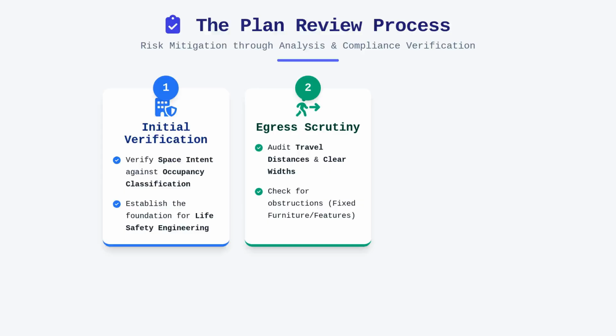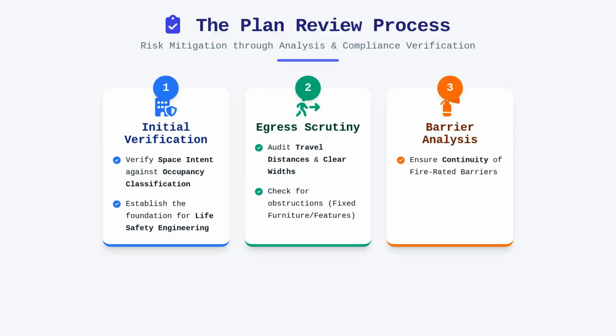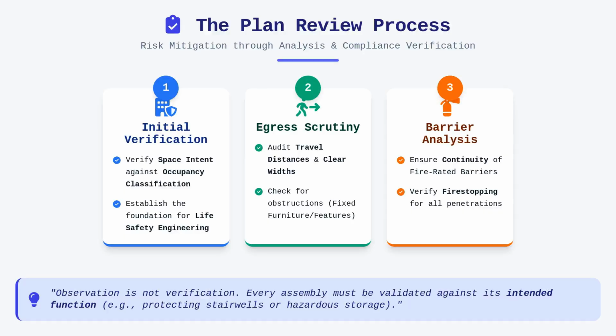This requires a careful examination of floor plans where we check for the continuity of fire-rated barriers, ensuring that vertical and horizontal penetrations are addressed through adequate fire-stopping details. It is not sufficient to simply observe a wall on a plan. We must verify the fire resistance rating of the assembly against its intended function, such as protecting a stairwell or a hazardous storage area.